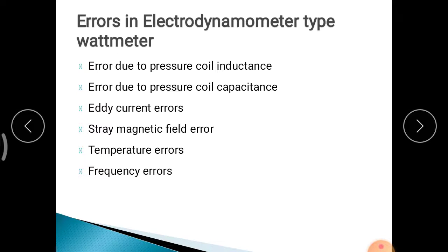Temperature errors occur because current flow produces a heating effect, which changes the resistance of components, altering instrument readings. To avoid this, low temperature coefficient materials such as manganin are used. Frequency errors occur because the supply frequency may vary slightly from 50 Hz — such variation changes the self-inductance of the coil, causing errors in readings. This covers construction, advantages, disadvantages, and errors of the Electrodynamometer type Wattmeter.